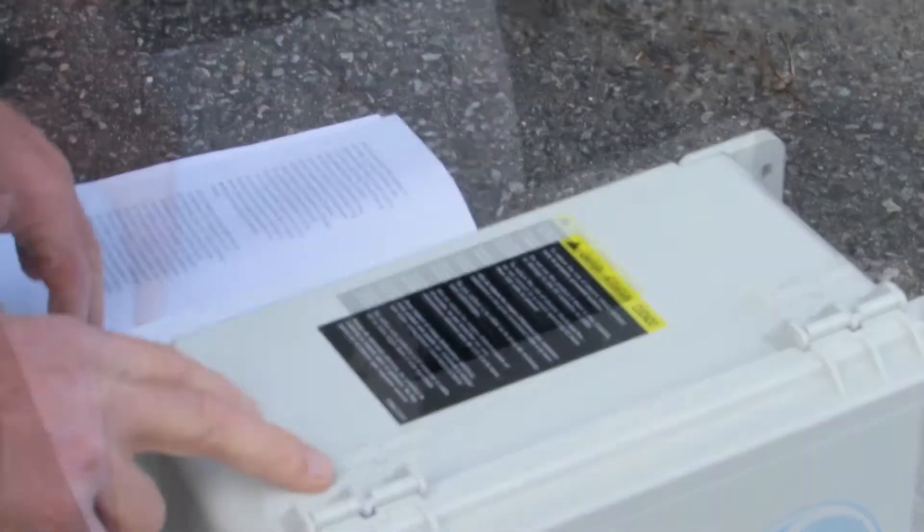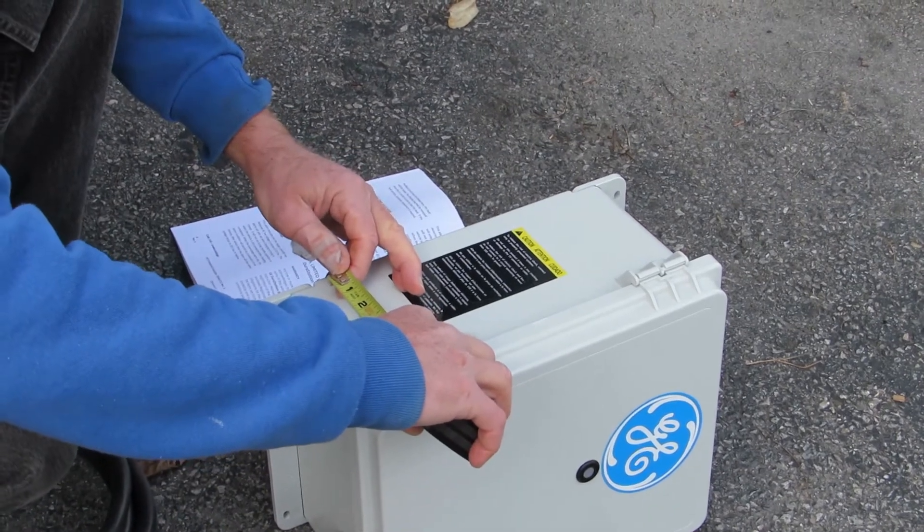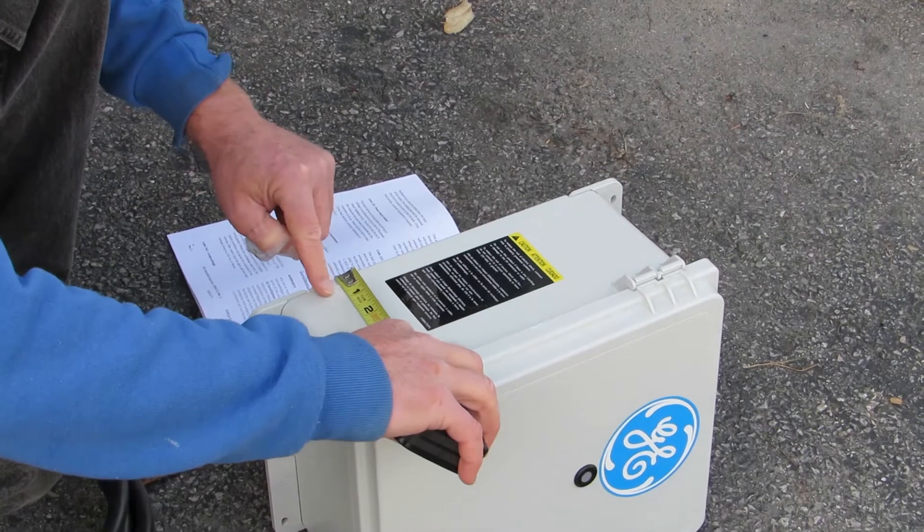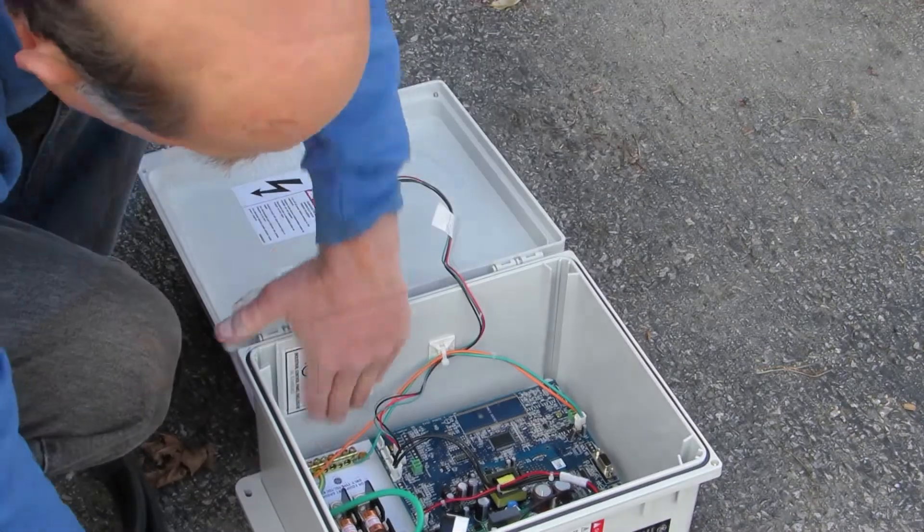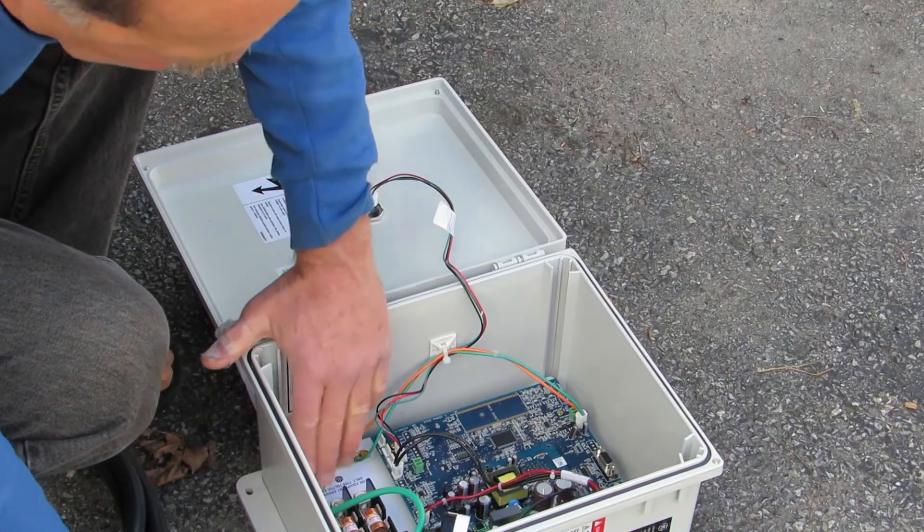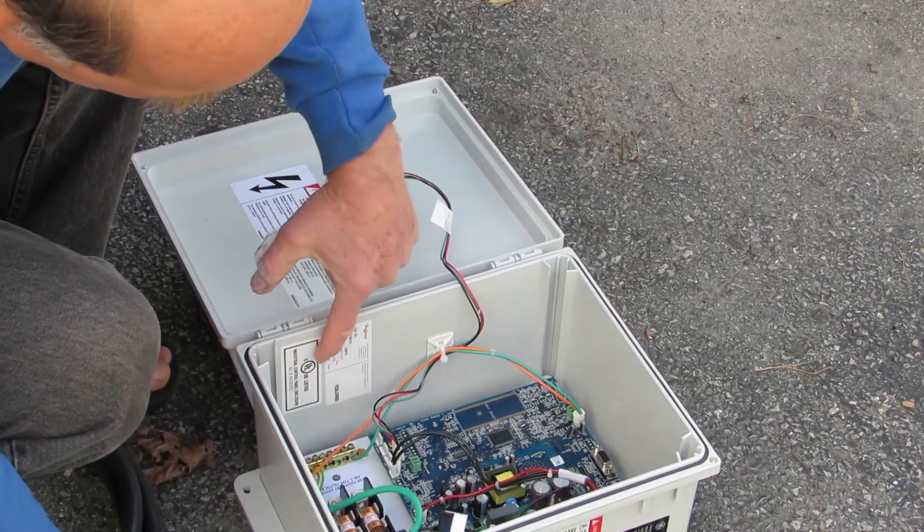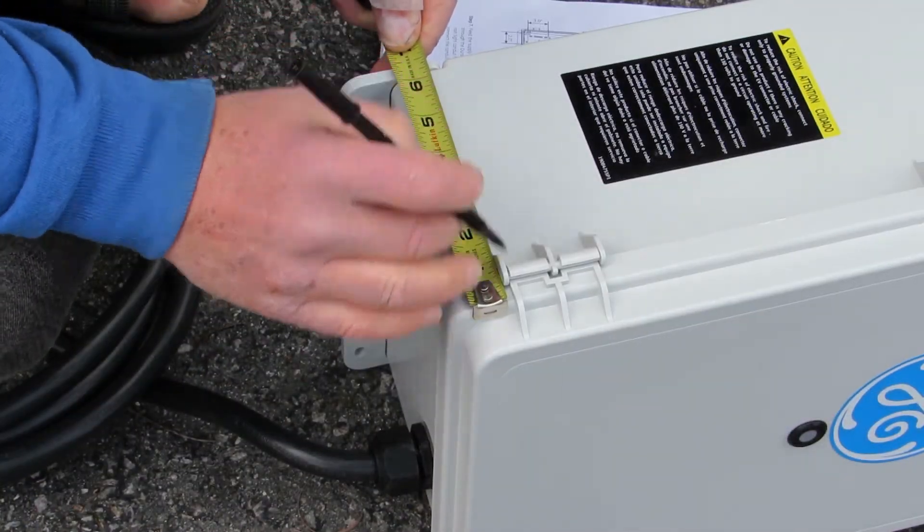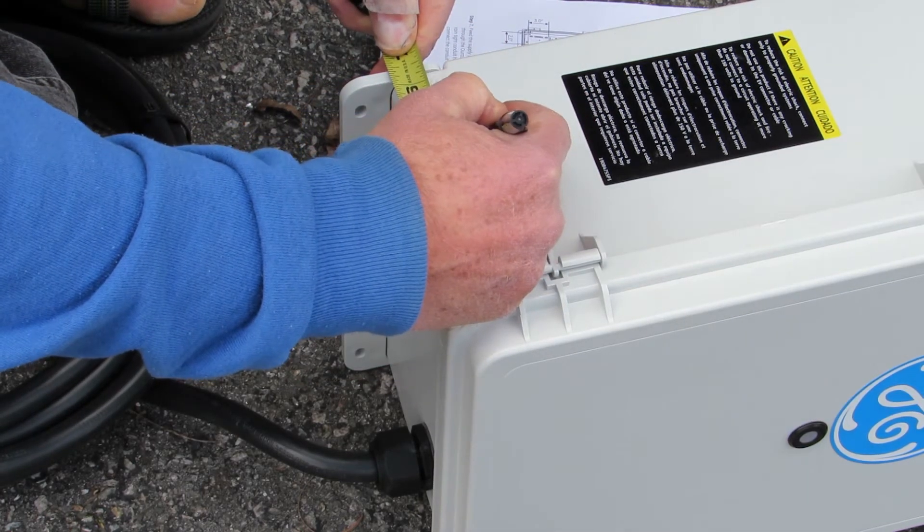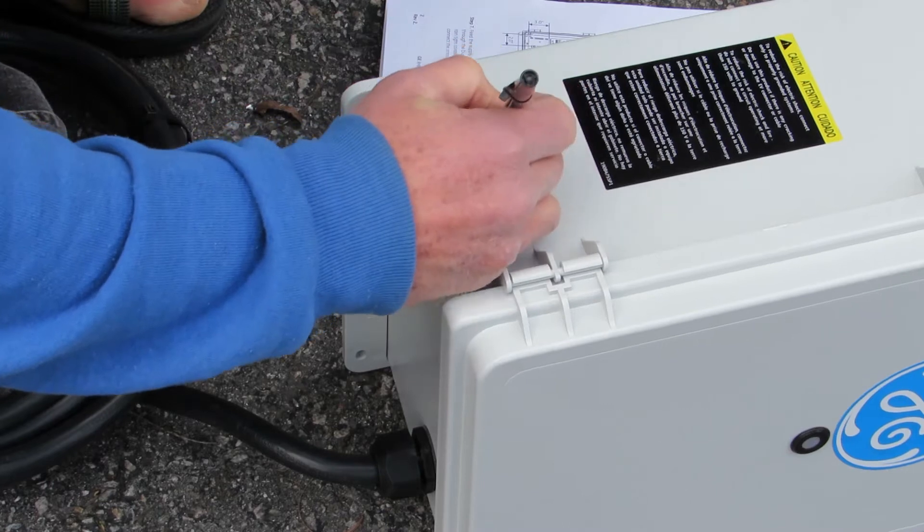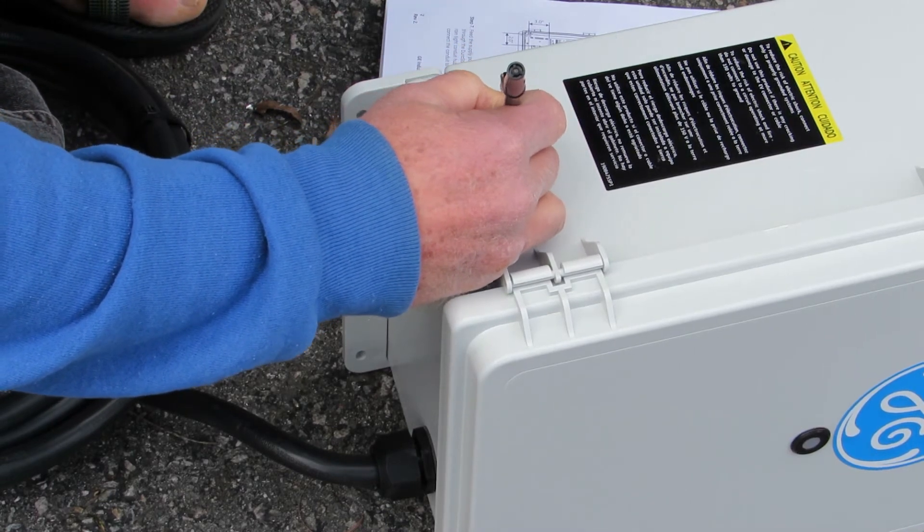So that's right here. This is the left side. They say that it should stay within three inches of the bottom and within five inches from the cabinet. I'm going to open this up to take a look. I want to bring it actually as low as possible because the wires are going to end up here and here, which are deep into the cabinet. I don't want to come in way up here and then have to go all the way down here. I'm going to put it right at the limit of where they allow it. I'm going to mark the center hole at four and a half inches because I'm going to be drilling a one-inch hole. And I'm going to center it here, one and a half inches in. So this is the center of the hole that we're going to drill in the side of the cabinet right there.